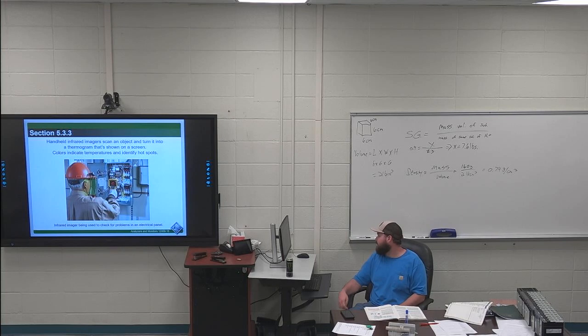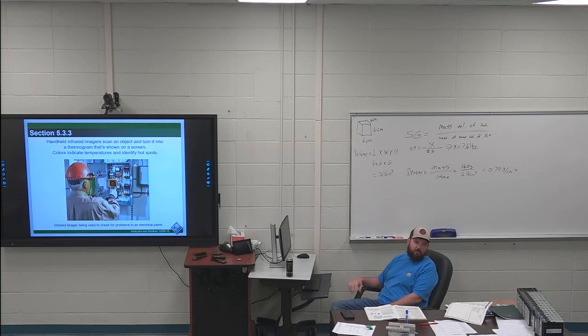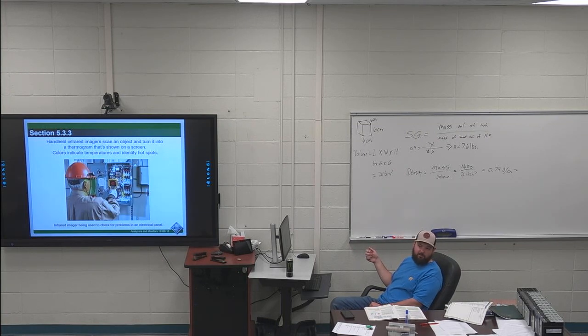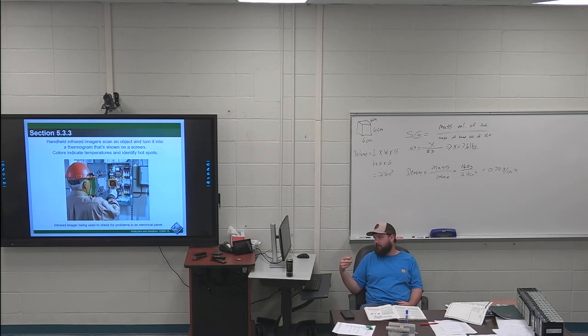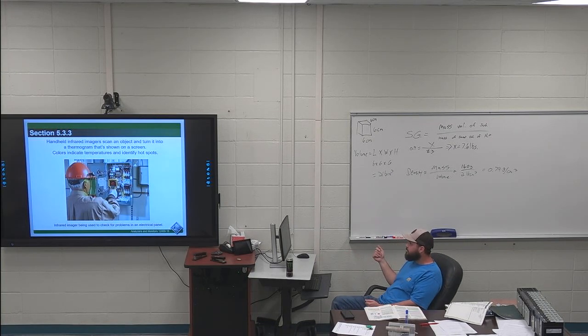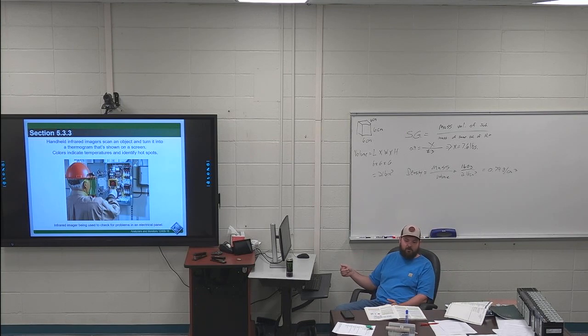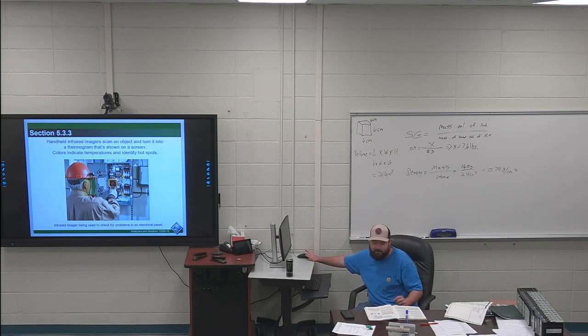I actually like what this guy is doing with this little thermal camera. When I was an intern at Goodyear, they made me walk around the air compressor room and take pictures of bearings, and also go to transformers. Transformers can get hotspots if windings have shorted together, or if different taps have not been terminated correctly. You can get hotspots in transformers, and you can see that through an infrared camera.